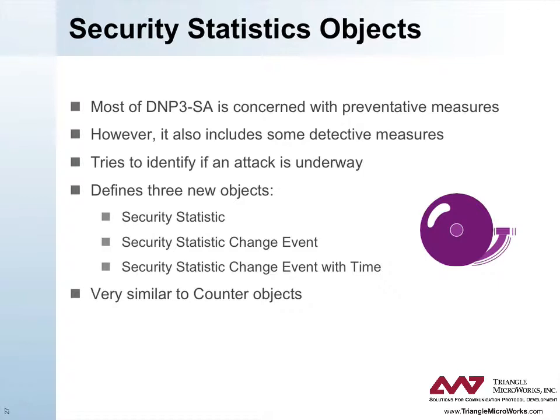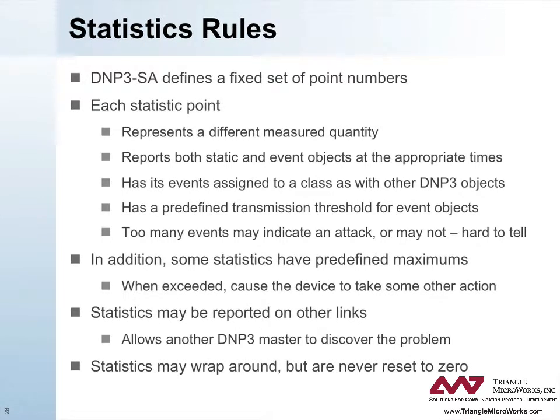The three new security objects are: security statistic, security statistic change event, and security statistic change event with time. These objects are very similar to counter objects. DNP3 secure authentication defines a fixed set of point numbers for statistics. Each statistic point represents a different measured quantity, reports both static and event objects at the appropriate times, and has its events assigned to a class, just like other DNP3 objects.